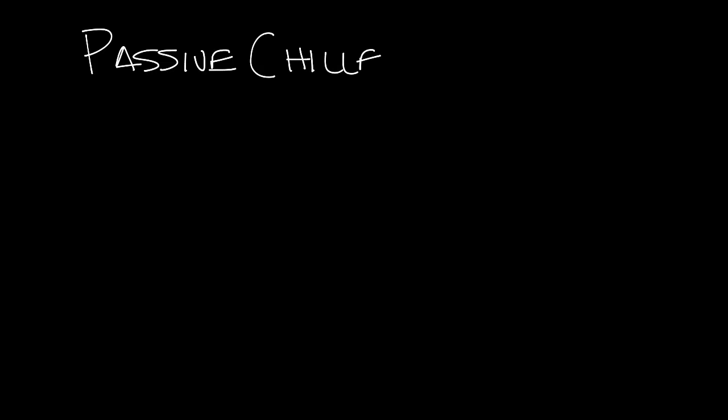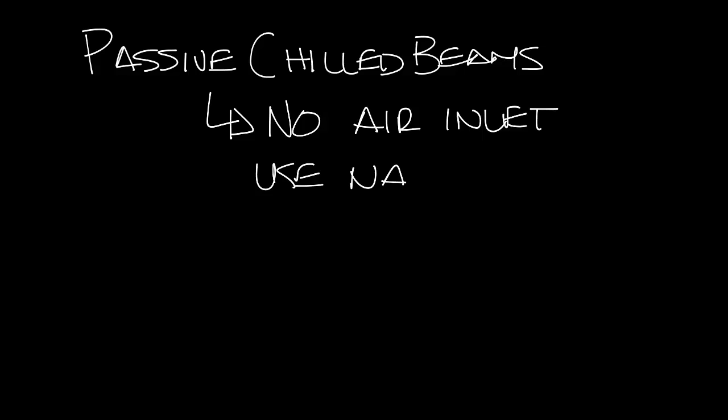Passive chilled beams have no supply air inlet. They use natural convection currents to cool the space, and a separate system is used to provide the ventilation air for the space.